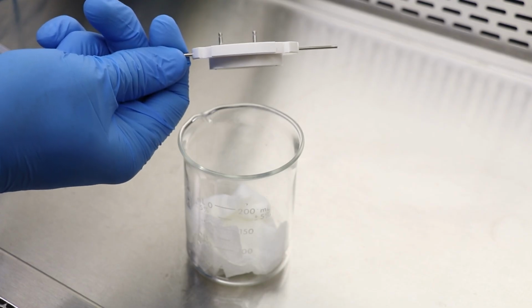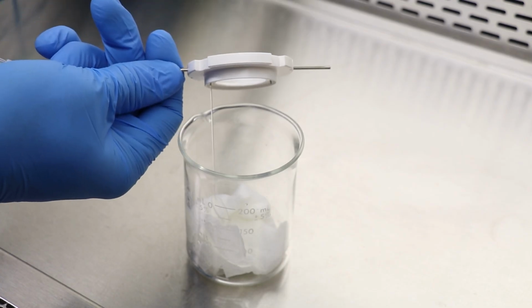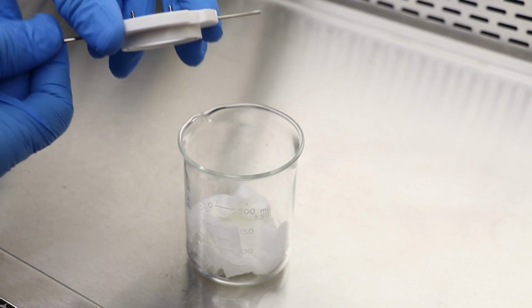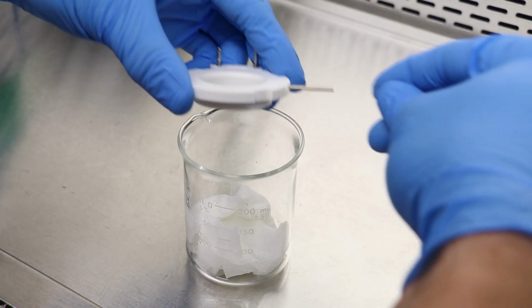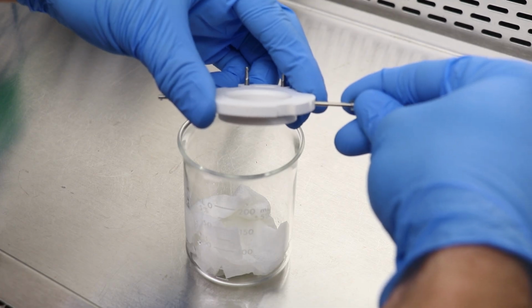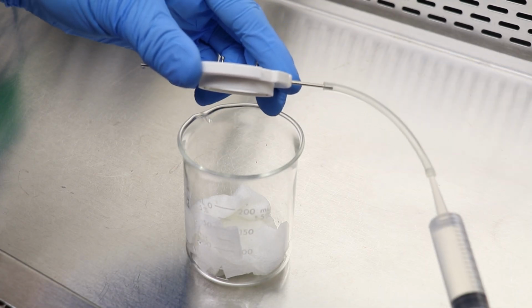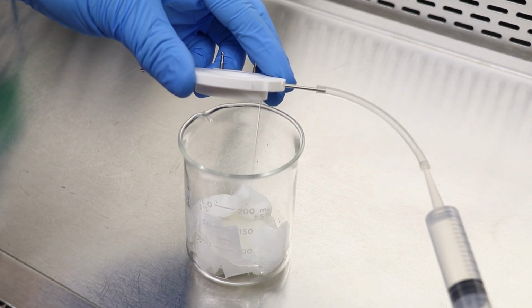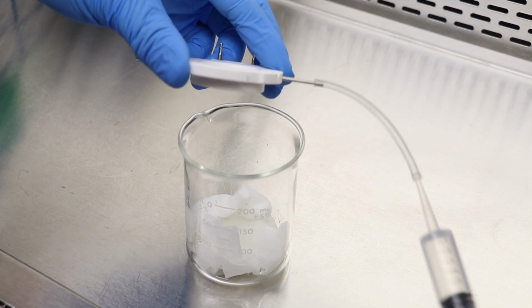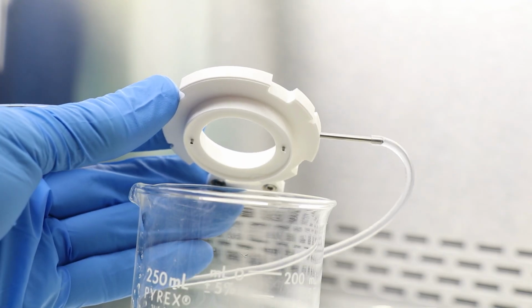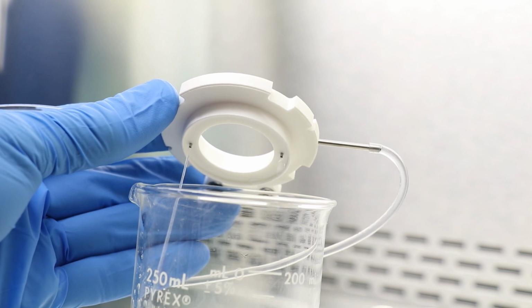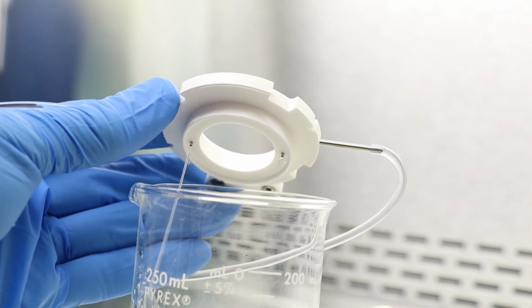If there is a restriction in flow from side to side or resistance when perfusing with a syringe, it may be time to clean more thoroughly than just a wash, rinse, and sterilization. How do you know if there's a problem? When perfusing, you should see a jet stream of water or alcohol from the lower, smaller ports of the top.